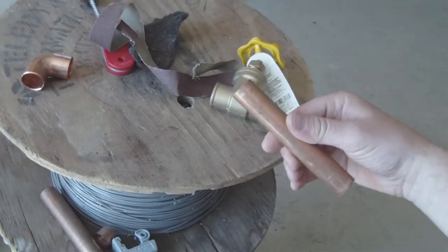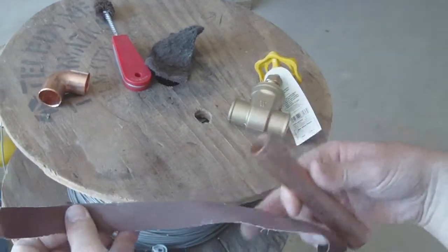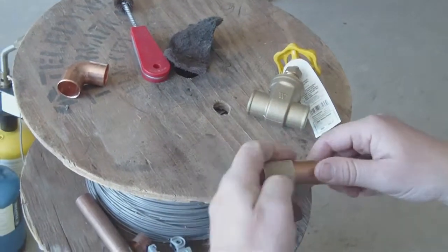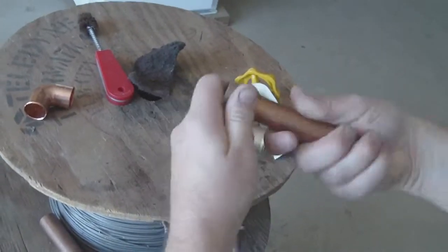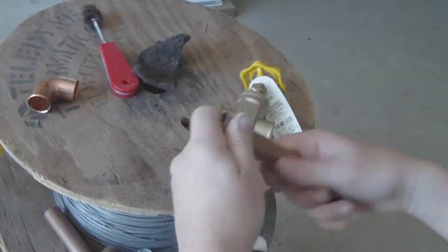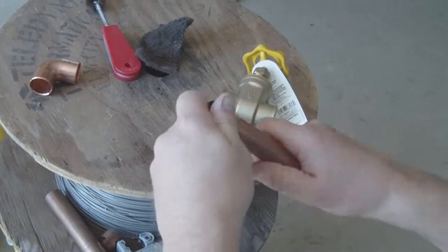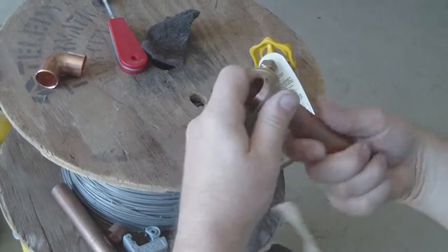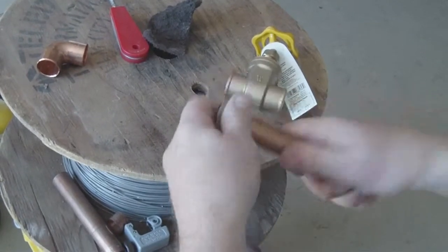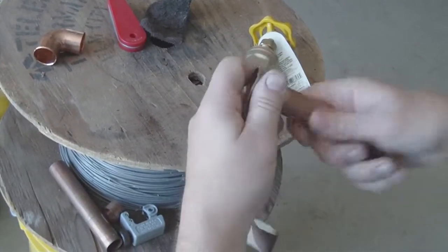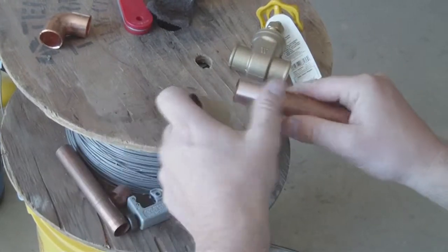Now doing the pipes, there are two different means of doing this. The most common way is to take a roll of sandpaper and just work your way around the edge. In the last episode, you saw that we know there's three-quarters of an inch that that copper is going to fit into the fitting and into that gate valve. So we could either take it down to an inch or slightly past three-quarter. I usually like to go about an inch. I want to go a little bit beyond the actual end of that fitting. And there's a few reasons for that. Just kind of like the edge there that I did, I want this nice and shiny. That's getting pretty good. That looks pretty shiny right there.